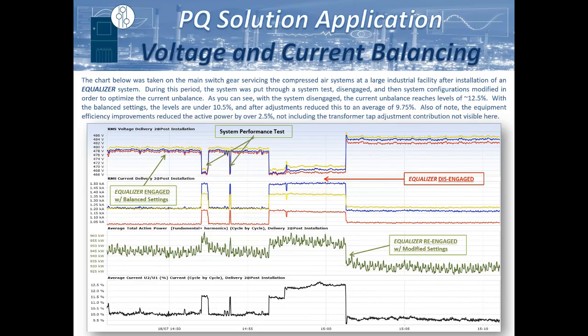The plant's objective for this specific project was to optimize their energy consumption and get the best efficiency they could. I was logged in and looking at their data while the maintenance manager was at the system, with the system engaged under typical settings. You can see the voltage was right about 478. We did some system testing, then turned the system off for a while and customized the controller settings. Instead of basing its compensation on the average of all three legs, we told it to base the compensation on the average of these two top legs.